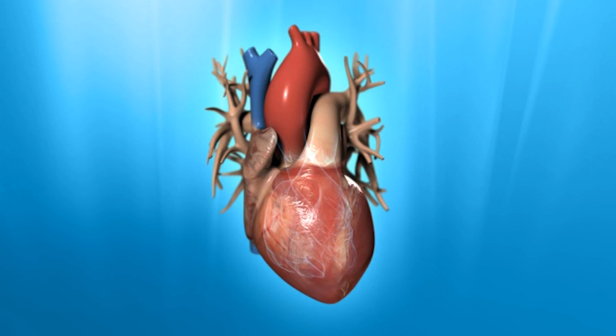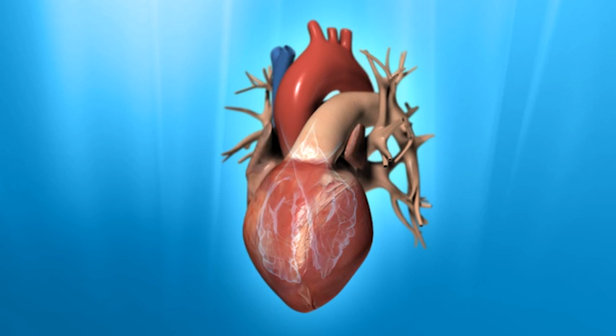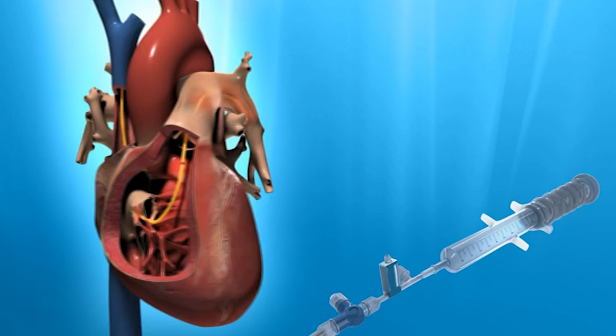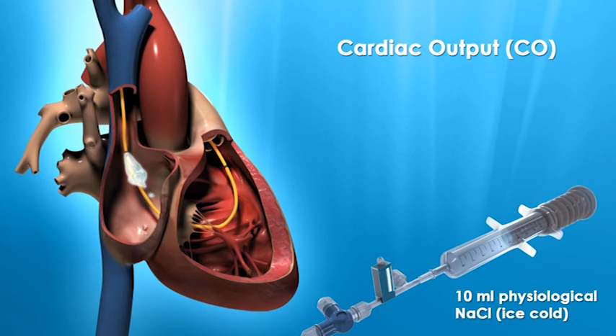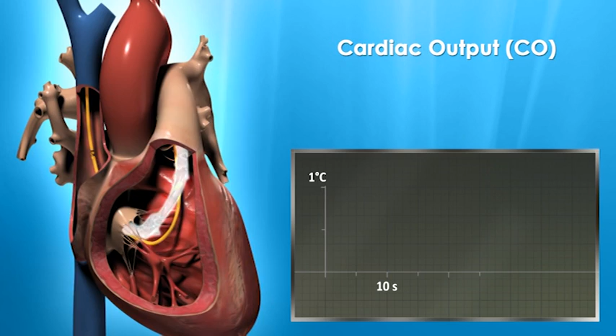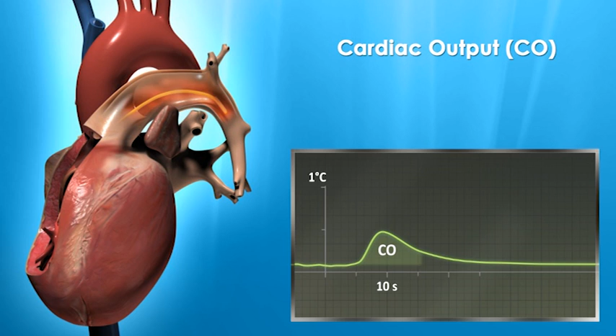Cardiac output is an important parameter influencing blood perfusion of the organs. To establish its value, the thermodilution principle is employed. After the correct position of the catheter's proximal lumen has been confirmed, 10 milliliters of ice-cold physiological sodium chloride are injected. The speed at which the cold liquid is diluted by the bloodstream depends on cardiac output. From the temperature measurements carried out over time at the tip of the catheter, CO is calculated by the cardiac output computer.